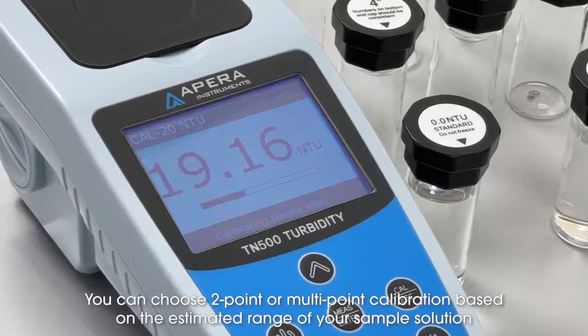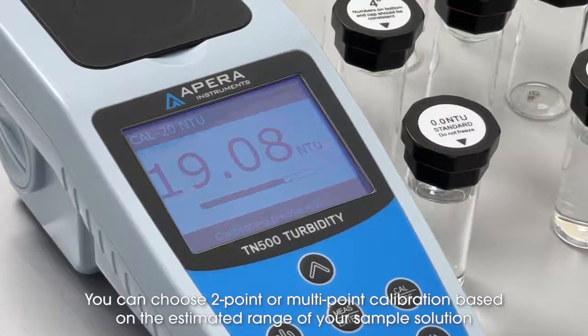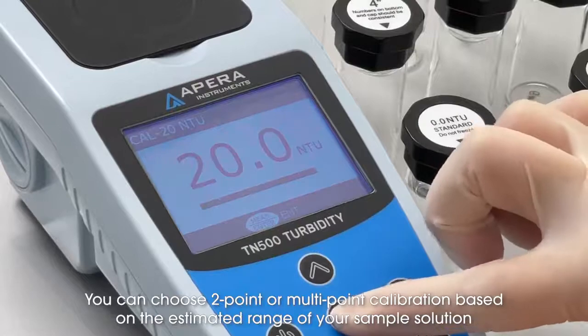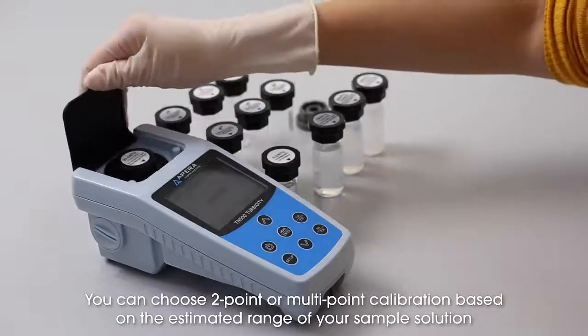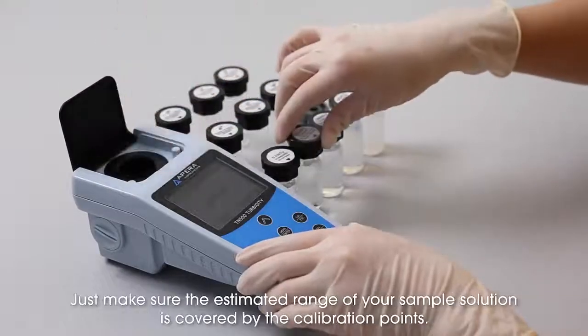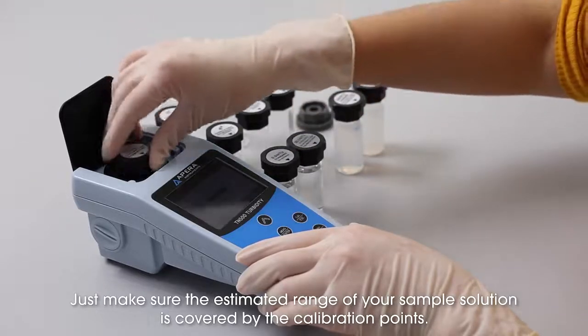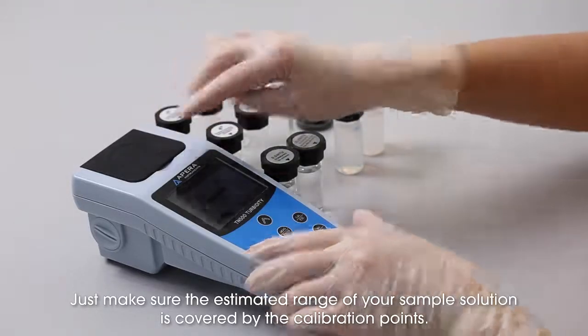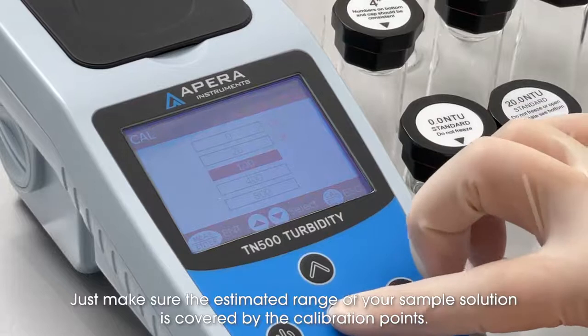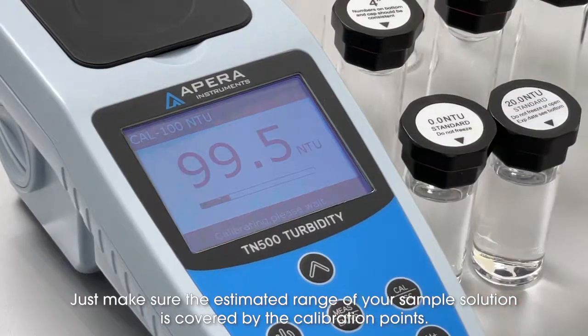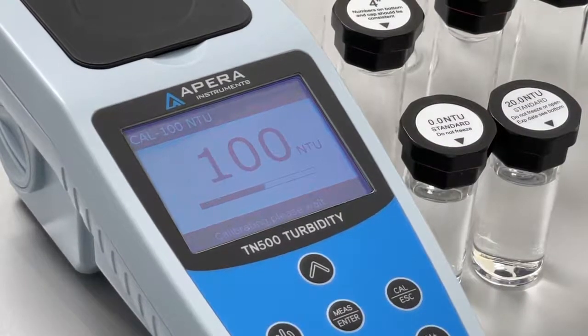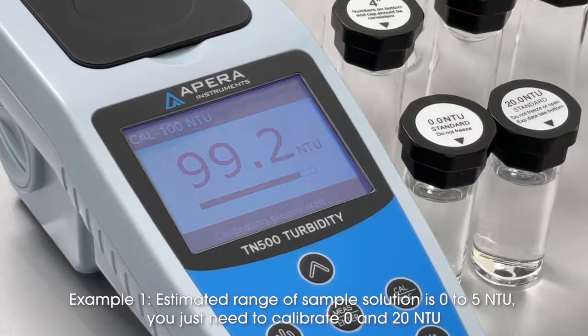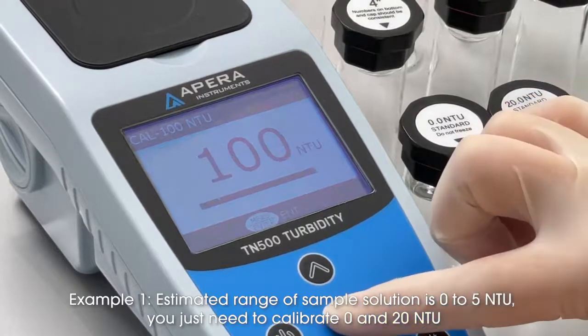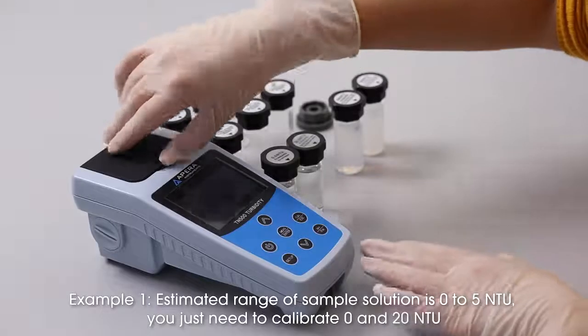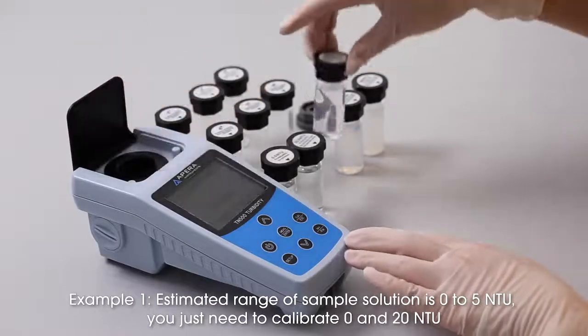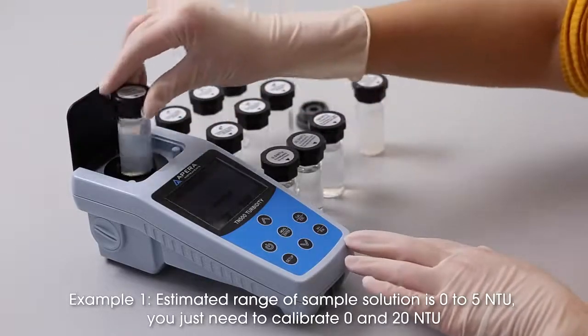You can choose 2-point or multi-point calibration based on the estimated range of your sample solution. Just make sure the estimated range of your sample solution is covered by the calibration points. Example 1. Estimated range of sample solution is 0 to 5 NTU, and you just need to calibrate 0 and 20 NTU.